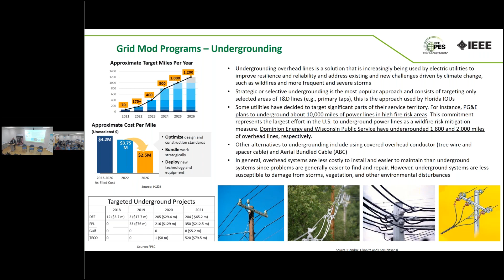FLISR is a program that is very common for some utilities. When they talk about grid modernization, they talk about FLISR, which means fault location, isolation, and service restoration. What FLISR does is automate the outage management and restoration process. When there is a fault in the grid, usually the distribution grid is meshed. So it's a mesh, but it's operated radially. Feeders have normally open points, connections with neighbor feeders. They are not networked like the transmission grid. So typically, when there is a fault in a feeder, the idea is you isolate the faulted area using equipment like switches or reclosers, and then you reconfigure the grid using neighbor feeders so you can restore service to other clients.